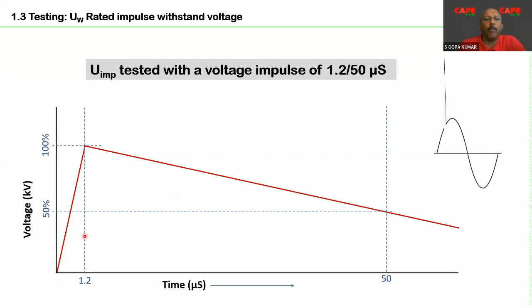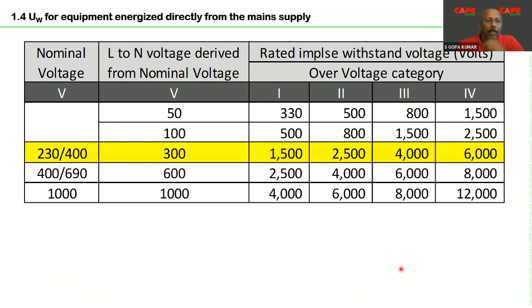And this voltage waveform looks like this: in 1.2 microseconds, it goes from zero to peak. Let us say the withstand voltage is 5 kV. So the voltage goes from zero to peak in 1.2 microseconds, and it comes to half of the peak. Let's say 5 half is 2.5. So 0 to 5 kV in 1.2 microseconds, and back to 2.5 kV in 50 microseconds. And this is the standard wave shape which is used for the voltage impulse test. So for every equipment, the manufacturer should test the equipment with this kind of an impulse voltage.